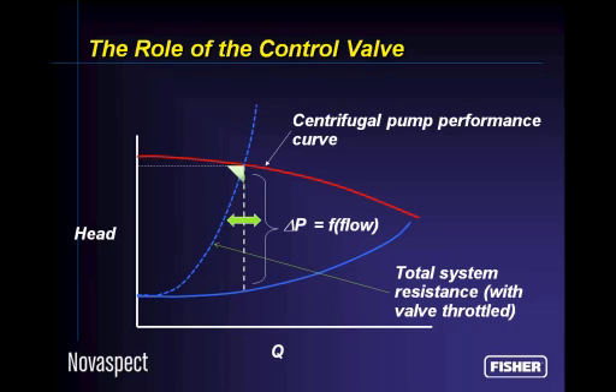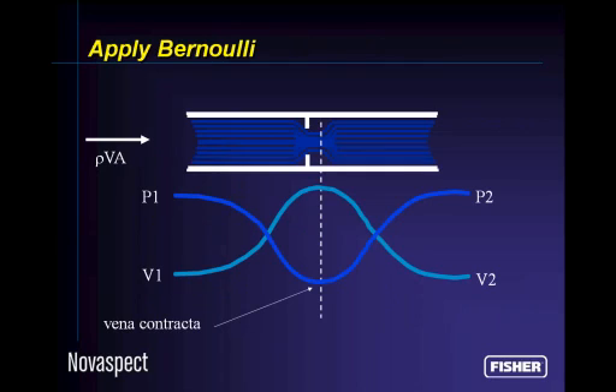What is obvious about what we've just done? When the valve was wide open, we had a very low differential pressure across the valve, but when we throttle the valve to a fairly closed condition, the pressure drop across the valve increases substantially. We have to worry about this condition because differential pressure is our enemy. It's what causes cavitation and flashing. Let's look into this a little further. What are the actual physics that are going on?